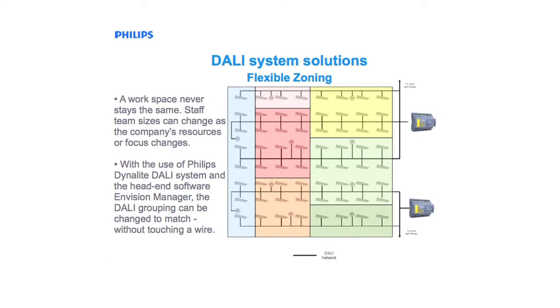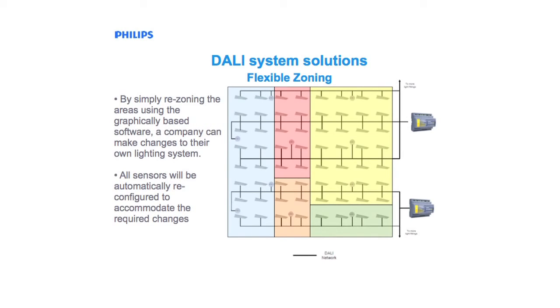Over time, a project's requirements change and areas need to be rezoned. To adjust the lighting zones when required, typically would require a professional commissioning technician or a qualified person to manually adjust the areas. With the use of the Philips Dynalite head-end software map view, a facility manager is able to re-coordinate the zones to suit. Using the software, a facility manager may simply delete a work zone, then regroup the lights as they see fit. They may regroup the lights across multiple DALI universes across multiple networks.